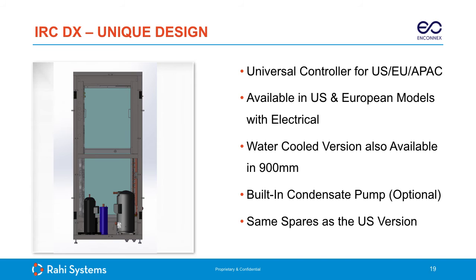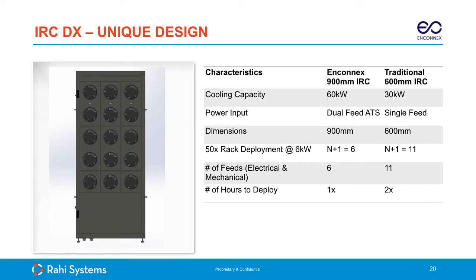Let's go to the next slide. Here's a design comparison of a 50 rack pod at about 6 kW load per server rack. When we did the comparison to a traditional IRC on the marketplace, pretty much all the other systems are 600 millimeter. This one's a little bit wider, but we looked at it. We actually derated the system based on a higher entering water temperature, so we were looking at it at a rating of about 60 kW.